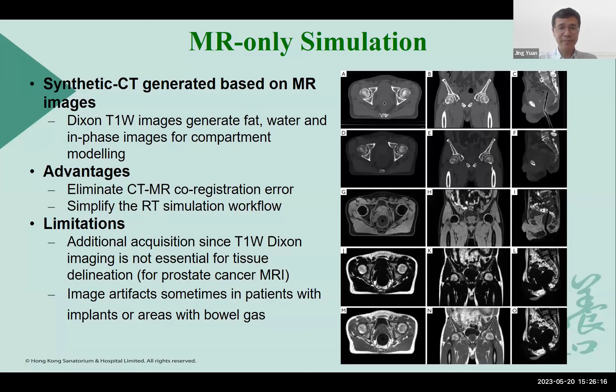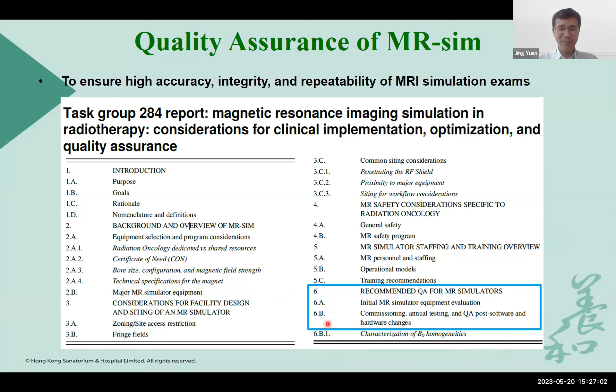QA of MR-Sim is crucial to ensure high accuracy, integrity, and repeatability of MRI simulation exams. So QA is also an important routine duty for medical physicists. Although MR-Sim QA has not been well standardized for different centers, there are still some general considerations. The AAPM Task Group 284 report is a very good reference document in this field and gives recommendations on the QA tests for MR scanners in the document, in Section 6, in this blue block.